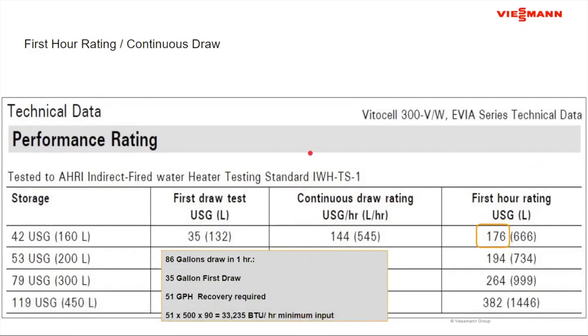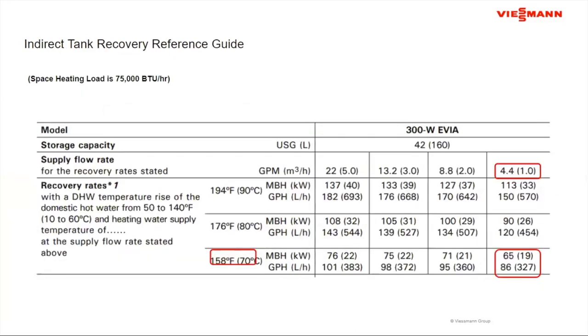And if I take that 51 gallons and convert it over to BTUs, I multiply that by 500, I multiply that by 90, my temperature rise, that's telling me I need 33,000 BTUs of energy to generate hot water. So quickly I look at that number, I look at the boiler that's going in, 75,000, and it's considerably less. So I think I can start to work with this number and come up with a true boiler size for my application, okay?